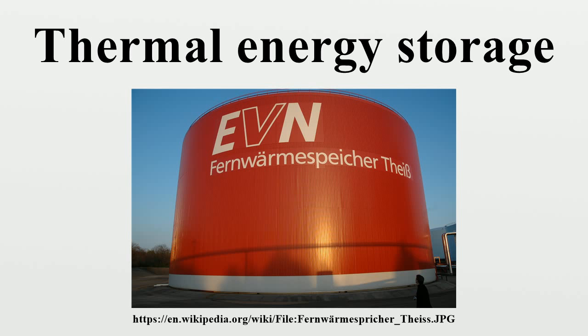Pumped heat electricity storage. In pumped heat electricity storage, a reversible heat pump system is used to store energy as a temperature difference between two heat stores. Isentropic One system currently being developed by the UK-based company Isentropic operates as follows. It comprises two insulated containers, a hot vessel storing thermal energy at high temperature and high pressure, and a cold vessel storing thermal energy at low temperature and low pressure. Both vessels are filled with crushed rock or gravel which acts as the heat storage medium. The vessels are connected at top and bottom by pipes and the whole system is filled with the inert gas argon.